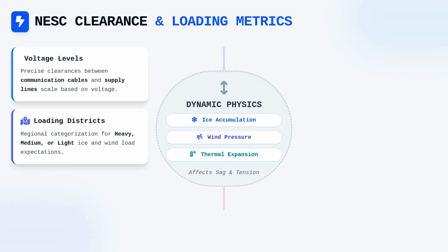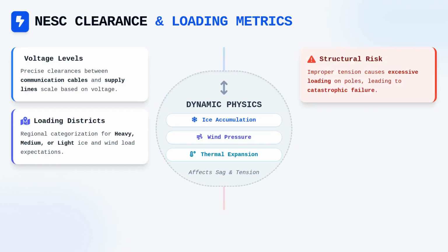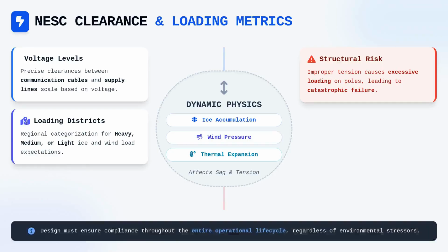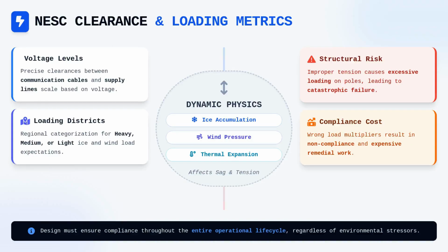The physics here are uncompromising, as improper tension management can lead to excessive loading on utility poles, potentially resulting in catastrophic structural failure. Every design must include a thorough assessment of these environmental variables to ensure that the installation remains compliant throughout its entire operational lifecycle. Failure to apply the correct load multipliers for your specific region can render an entire project non-compliant, necessitating costly and complex remedial work on existing utility infrastructure.